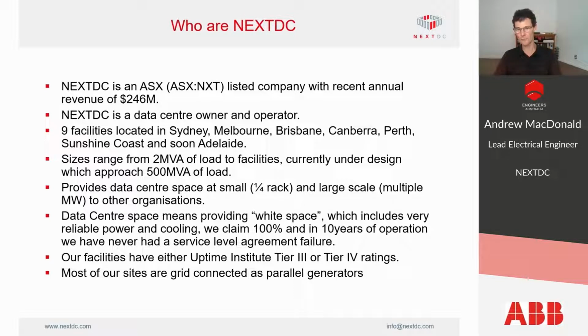What we sell is rack space to customers, and the sizes range from a quarter of a rack, which is not very much, up to large scale cloud and web service providers which take multiple megawatt tenancies. In a data center, we hear the term white space, which includes providing very reliable power and cooling to the racks. We claim 100% uptime, and in 10 years of operation, we've never had a service level failure with any of our customers. That means that we've had at least one of the 2 power supplies always on to all of the racks in all of our facilities, and we've always maintained cooling.